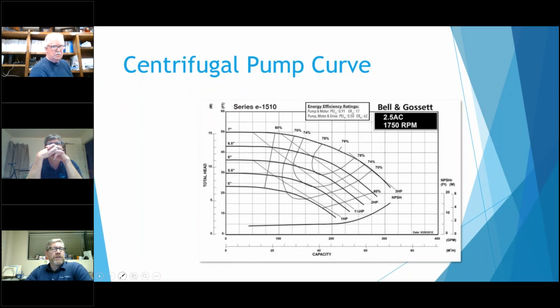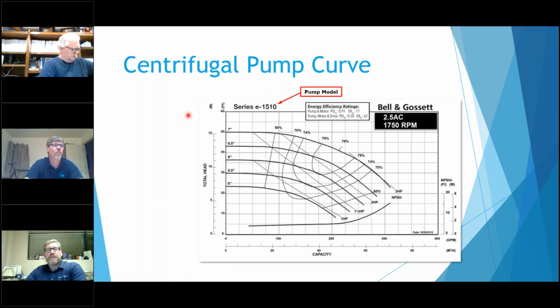Here's a pretty typical centrifugal pump curve. This is a pretty current curve, with a little more information than what they used to have in years past. We'll go over that, of course. The first thing we see is the pump model located up here, like the 1510 or the E1510. We've got size, max impeller, revision.